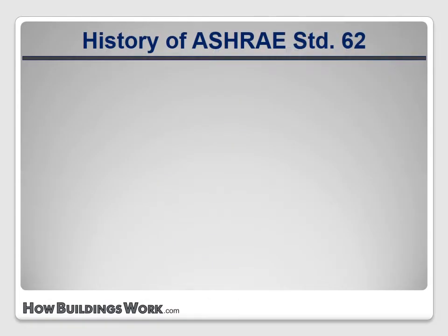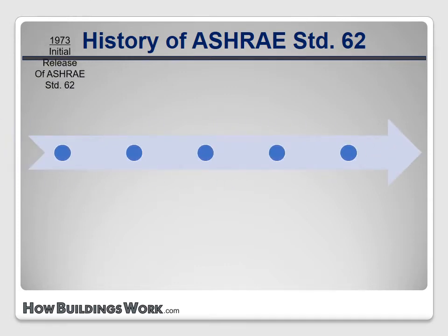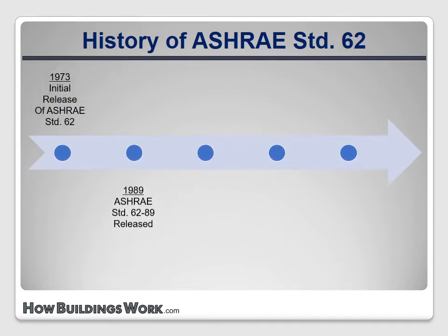ASHRAE Standard 62 was originally released in 1973. In 1989, a version was released that included a recommendation of air exchange rates of at least 0.35 air changes per hour, or 15 CFM per occupant. This recommendation was adopted by building codes and retrofit programs, and it's still in use today in some applications.